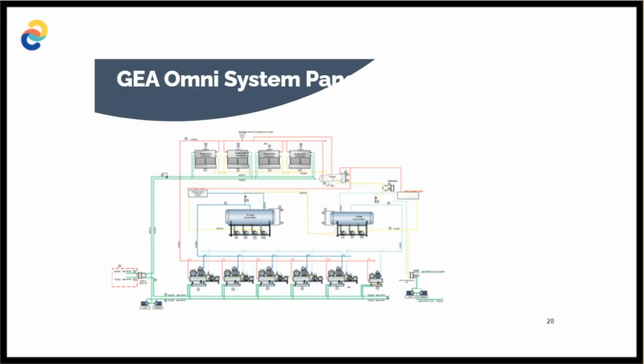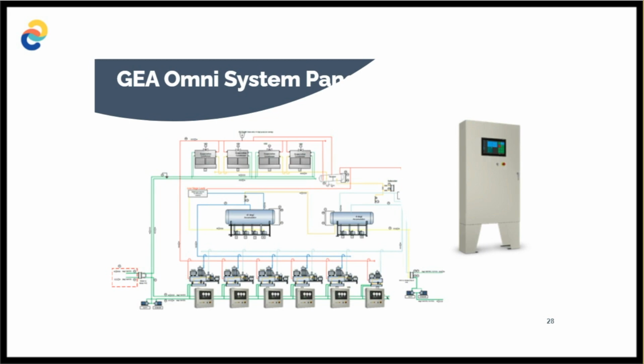I mentioned GEA is more than a compressor controller, so we can add the Omni as a system panel, whereby we can connect all the compressors and we can start to connect other features of the plant. So pumps, condensers, and even air coolers. And we do that by a feature called the Smart Connection Box. So on each of these individual components, we have a Smart Connection Box which takes in data and delivers that to the Omni system panel.